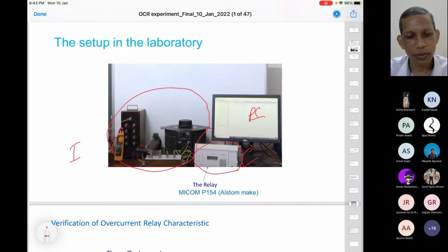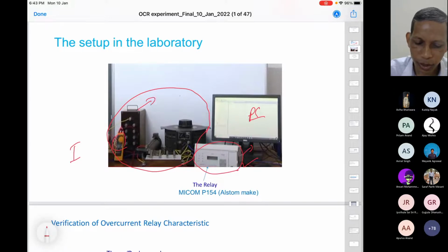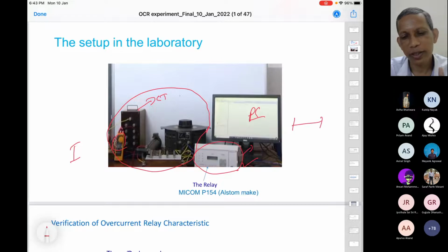If it is an impedance relay, we require voltage information also. This is a three-phase relay, so it requires IA, IB, IC, three currents as input to this particular relay. And these are about measurement systems. So this is about the current transformer also. We require a current transformer. See, in a system, the level of currents can be thousands of amperes, particularly during a fault.